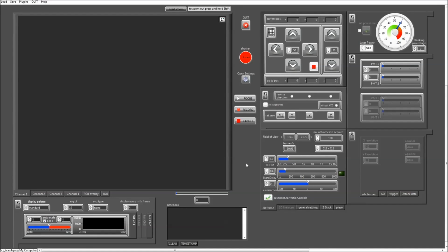Another functionality in the GFG is that it actually generates events whenever one of the variables is changed. So that means you can listen for events to occur whenever something changes in SciScan, whether it's a variable or a front panel element or a frame count in the background. Anything that happens will happen in terms of a change of a variable, and that will generate an event that you can capture in your standalone VI. So let me quickly show you how to do that.